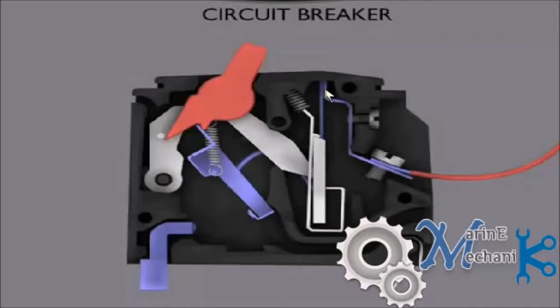The current comes through this blue wire and then it goes to the bimetallic strip, and here you can see behind there's one more conductor or metal piece which goes to this link. Whenever the circuit breaker is on, this will go and hit or make a contact here, thus the current supply is taken out through this terminal. So this is the input terminal and this is the output terminal, or outlet, in layman's terms. So now let's see what happens when it is working.